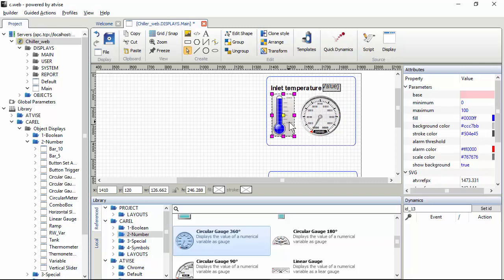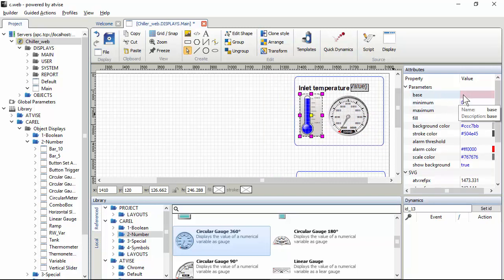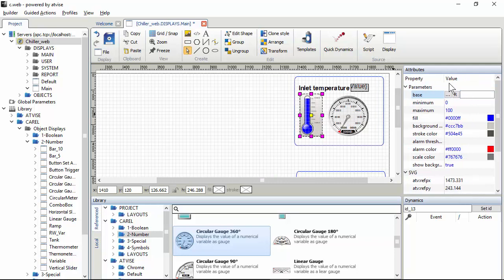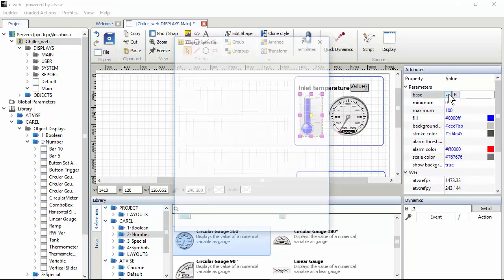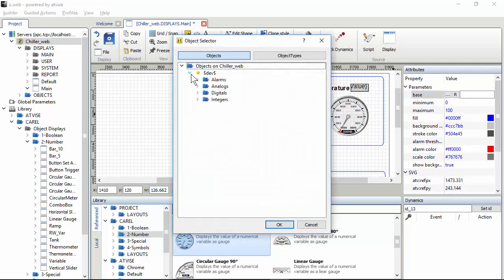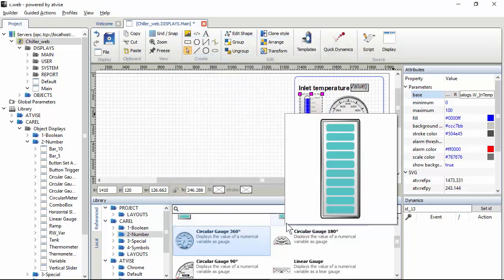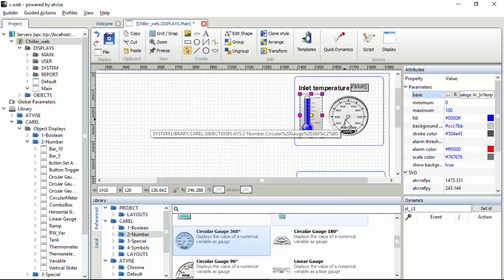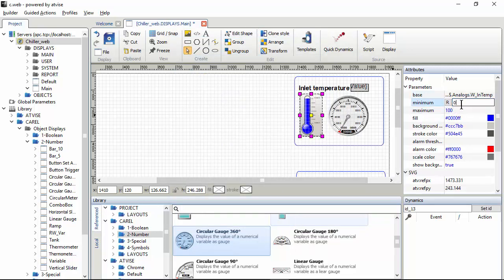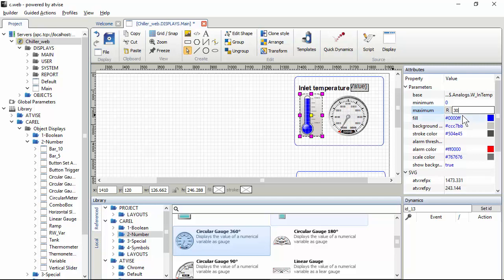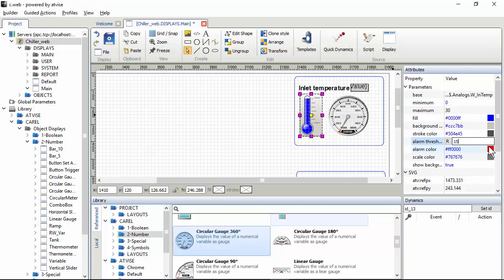For this, we select the variable analog water inlet temperature, and we can select the limit from 0 to 30 degrees. This widget features also a warning and alarm threshold. So when it reaches, for example, 15 degrees, the bulb color changes from blue to red. Okay, we will see this later.